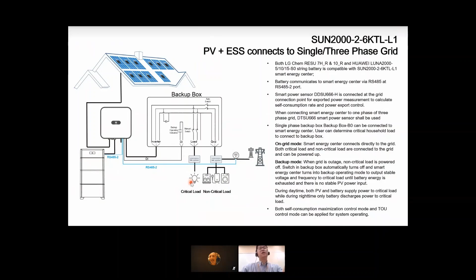When the grid power is on, whether they are critical loads or non-critical loads, they all run normally. But if the grid is down, then the auto switch here will be disconnected, so the non-critical loads get no power. But this manual switch here is connected, so power from the PV modules or the battery will be provided continuously to the critical loads. However, there is still a 3 second switchover time, so you need to wait 3 seconds to get the emergency power.